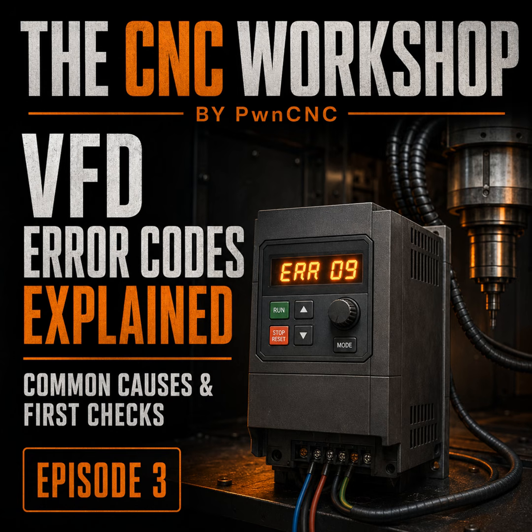The worst response is to keep resetting it and forcing the job to continue without finding out why it stopped. Especially because the spindle can stop while the CNC controller keeps moving. Yes, and that is an important safety issue. The controller and the VFD are separate parts of the system. If the VFD faults, the controller may not automatically know the spindle has stopped. It can continue driving a stationary cutter through the material. That can break the tool, damage the workpiece, damage the spindle, or put a lot of force into the machine.